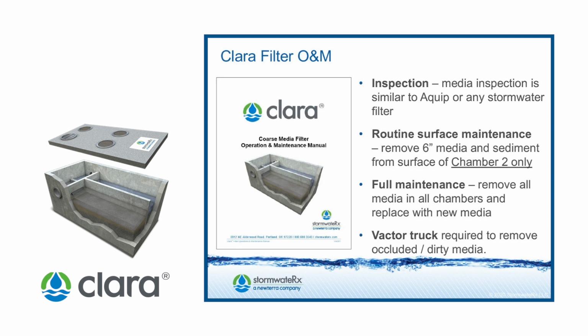If inspection is done during the actual operation of the Clara filter, please note if the filter is showing bypass or not. This would also be a very good indicator that the Clara filter needs either routine or a full maintenance. There are really only two types of maintenance activities associated with the Clara filter, the routine and the full.